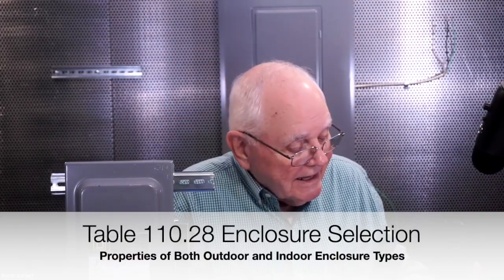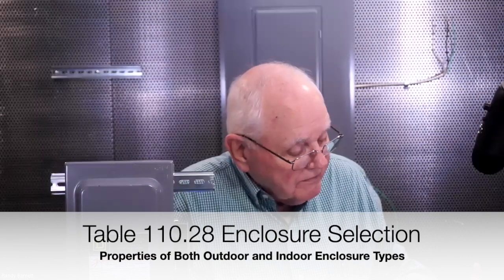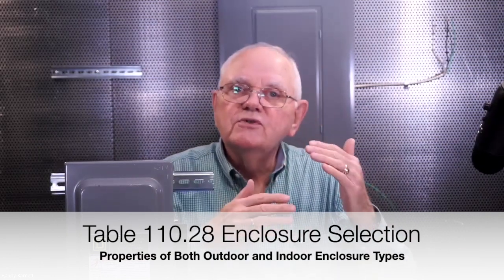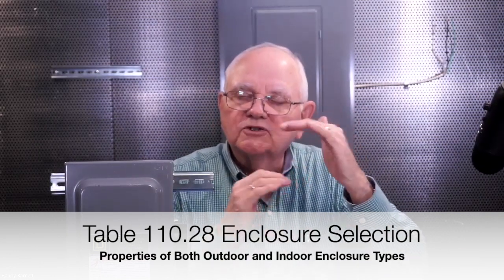Yes, it's in an enclosure, a safety switch, in a metal enclosure. There are different types of enclosures. This is a type 1 enclosure. It's good for pretty much falling dust indoors, and that's about it, really. Falling dirt, whatever. We can go to 110.28 though if we want to select another type of enclosure. So 110.28, let's take a quick look at that. Table 110.28, enclosure selection. It's divided up into two categories: outdoor enclosures and indoor.